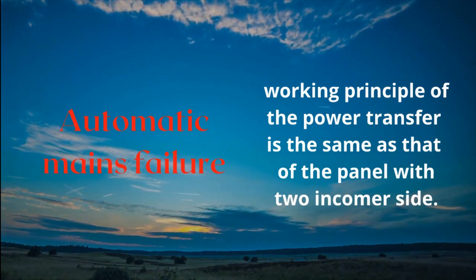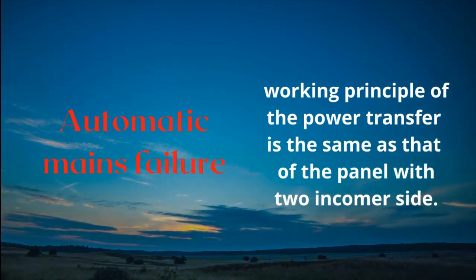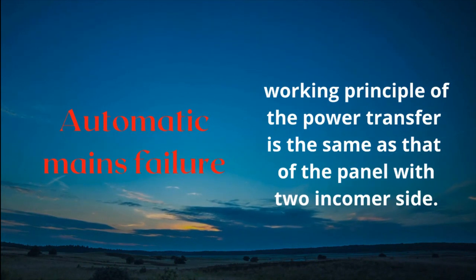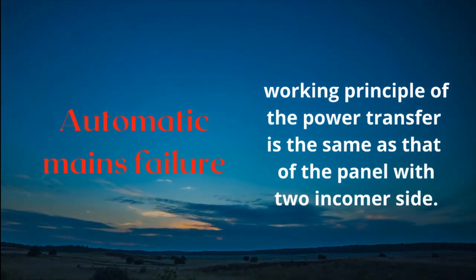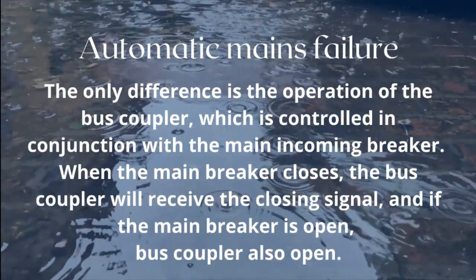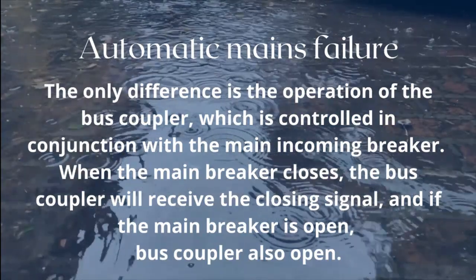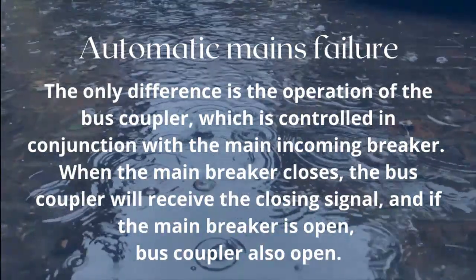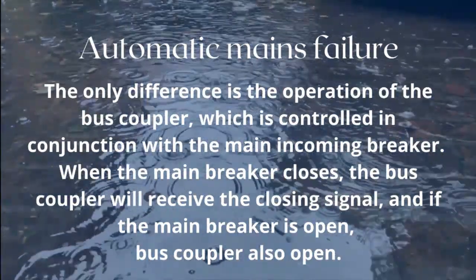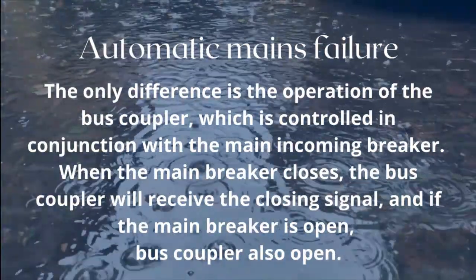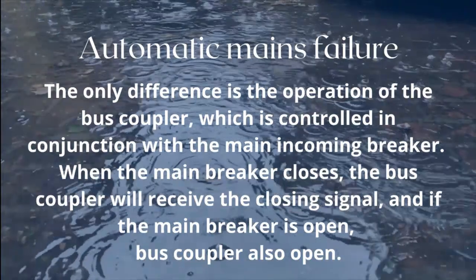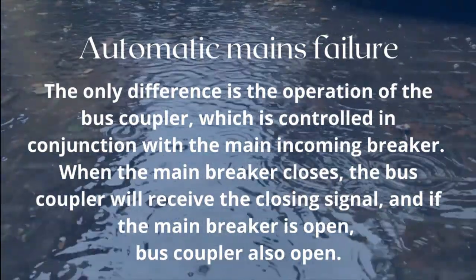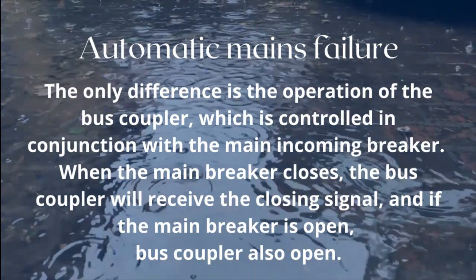The working principle of the power transfer is the same as that of the panel with two incoming sides. The only difference is the operation of the bus coupler, which is controlled in conjunction with the main incoming breaker. When the main breaker closes, the bus coupler receives the closing signal, and if the main breaker is open, the bus coupler also opens.